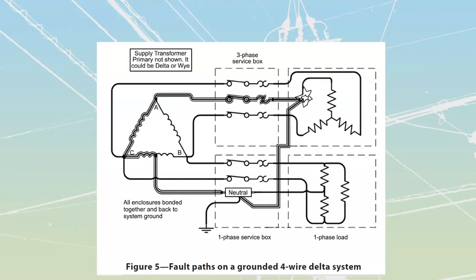If we have a single fault on the other three-phase set, the A phase, we're going to have a fault path that can be completed. If my A phase faults right here, current delivers from A, goes along here, hits that fault, goes back to the bonded can, and traces along the bonded can until it gets back to the neutral. Once it gets back to the neutral, it travels through part of my C winding and across my A winding.